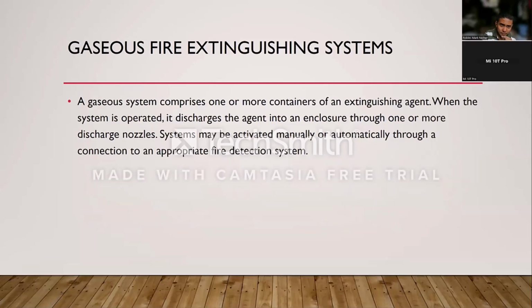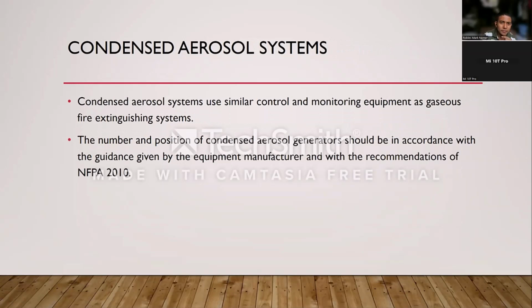Fire extinguishing systems. A system comprises 1 or more containers of extinguishing agent. When it is operated, it discharges the agent into an enclosure through one or more discharge nozzles. Systems may be activated manually or automatically through a connection to an appropriate fire detection system. Condensed aerosol systems use similar control and monitoring equipment as the gaseous fire extinguishing system. The number and position of condensed aerosol generators should be in accordance with the guidance and recommendations of NFPA 2010.